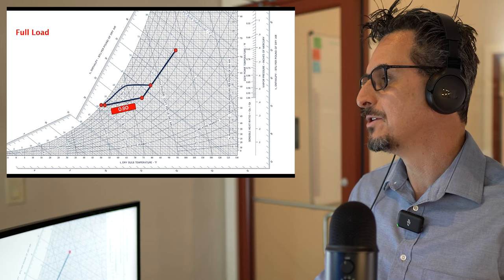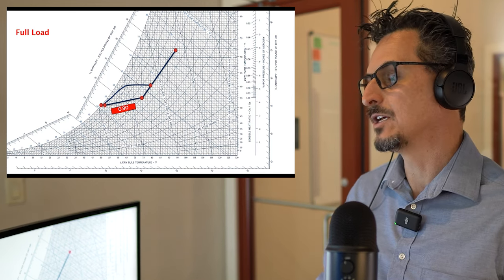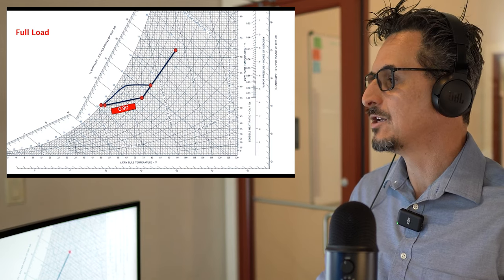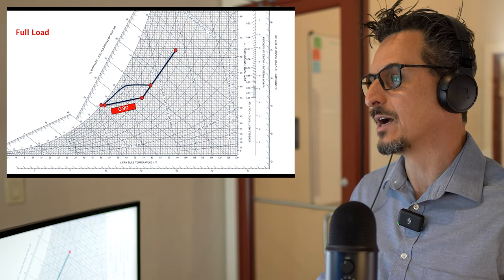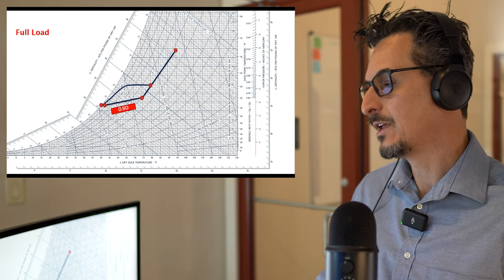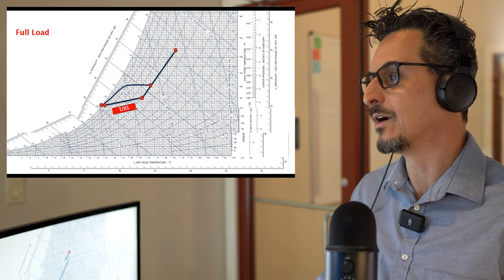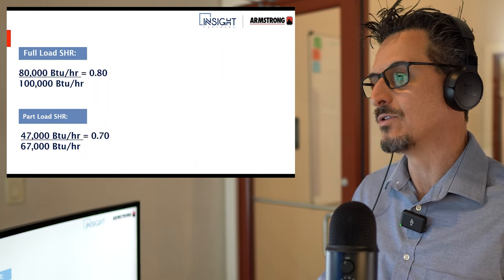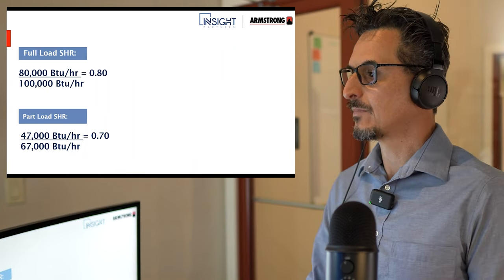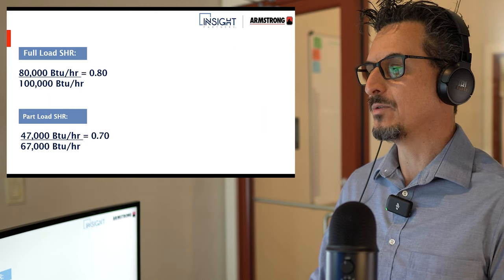It's worth noting that most systems are designed for sensible heat — temperature control only — and dehumidification is a byproduct. That's the vast majority of products. If they're designed properly, it's usually not a problem. But there are a lot of cases where we have to actively control humidity. Now we just looked at full load at 0.8 SHR — let's see what happens to this same equipment at a 0.7 SHR.